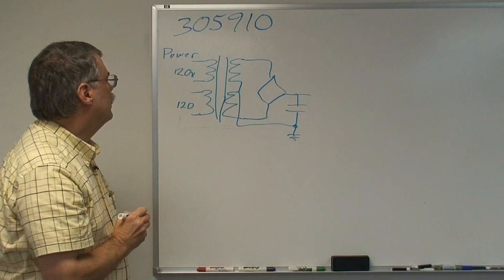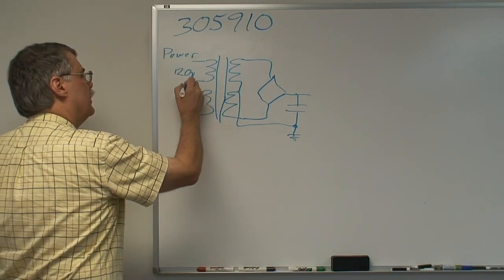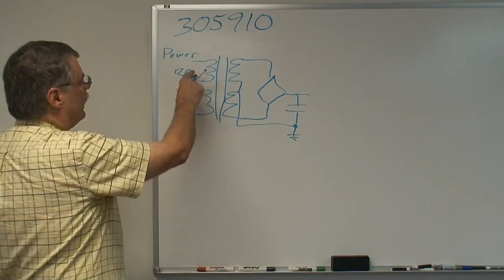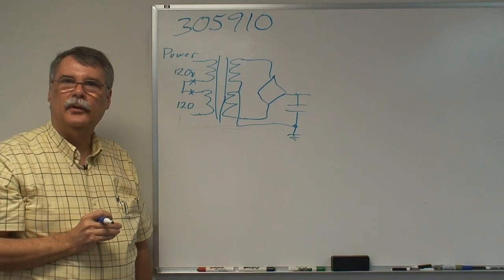Now with the two primary windings on this transformer that runs this thing, we have two choices. Each of these windings is 120 volts. So we can hook them up one way, that we can put a jumper from here to here, and that adds 120, 120, and we can operate this thing on 240 volts.